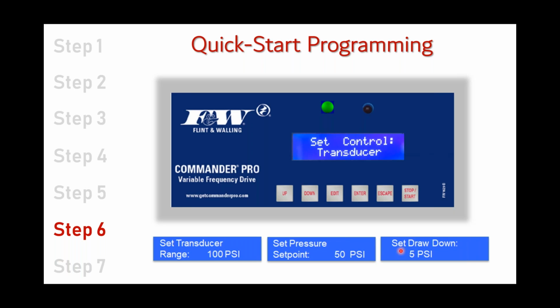But you do have the choices. I think if you wanted to change that for whatever reason, your choices are from 2 to 15 psi. But a 5 psi is typical. It's a factory setting, and so many times once you set the transducer, you look at the 100 psi, you go, yep, enter it. You look at the 50 psi, you either say yes or no there. If yes, 50 is all right, enter it. If you're going to change it, change it and then enter it. And then you get to the drawdown, 5 psi is okay, enter it.